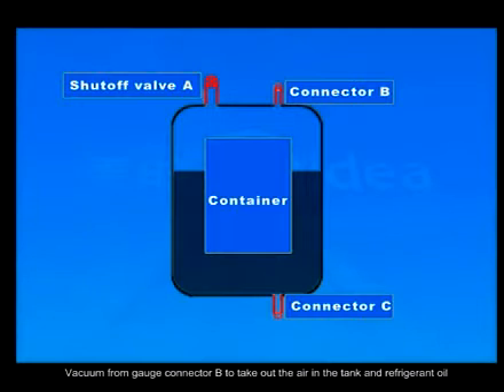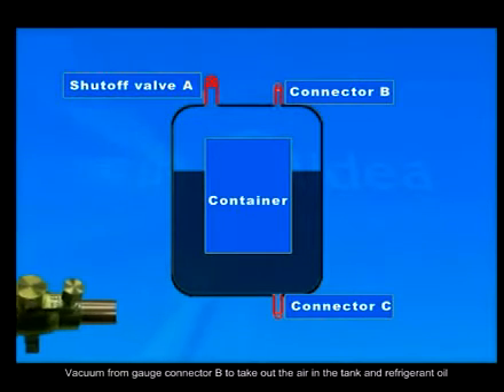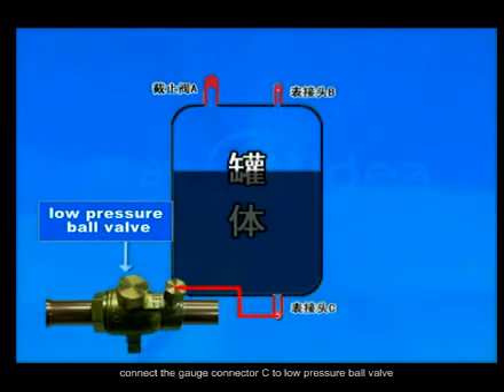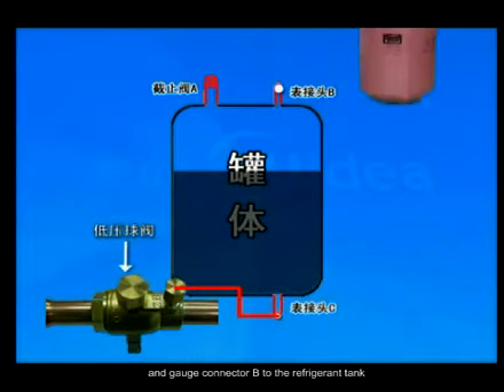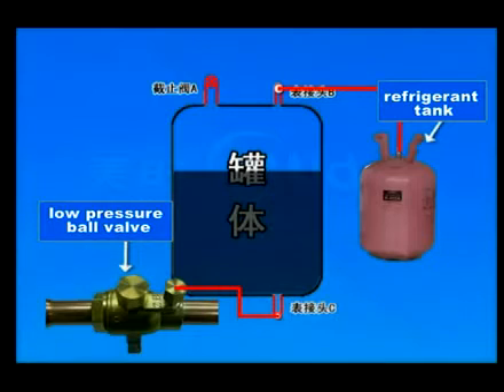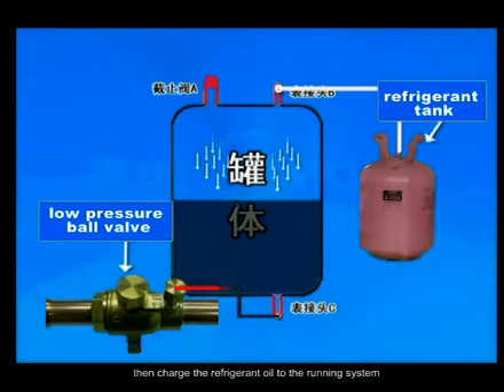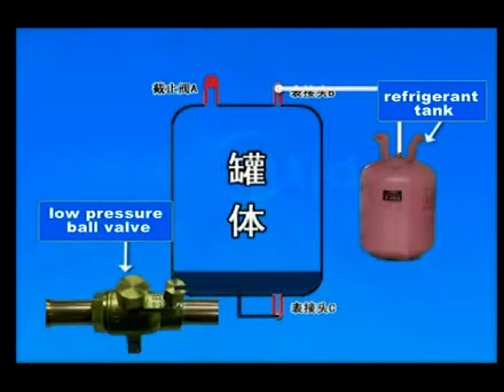Vacuum from gauge connector B to take out the air in the tank and refrigerant oil. Connect gauge connector C to the low pressure ball valve and gauge connector B to the refrigerant tank. Then charge the refrigerant oil to the running system by the pressure of the refrigerant in the tank.